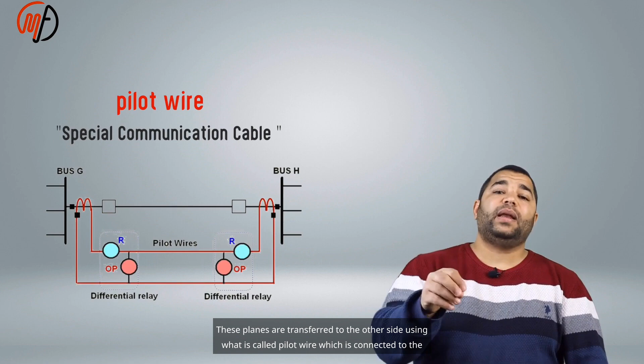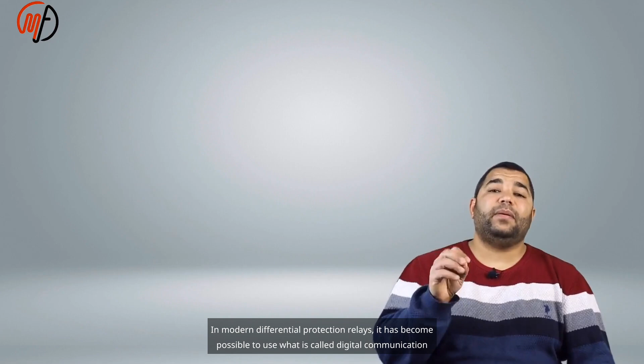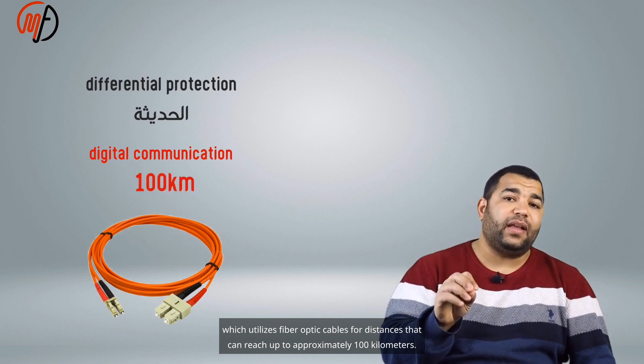This current transfer is done using what is called pilot wire, which is connected to the relay and is used for distances up to about 25 kilometers. In modern differential protection relays, it has become possible to use what is called digital communication, which utilizes fiber optic cables for distances that can reach up to approximately 100 kilometers.